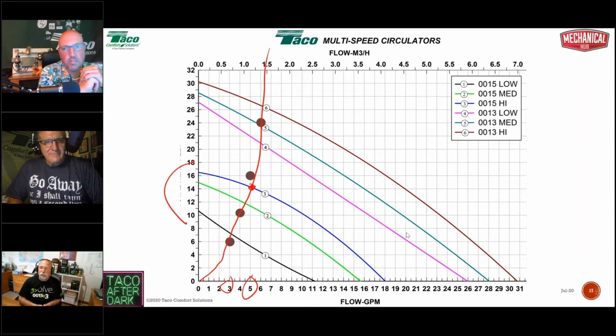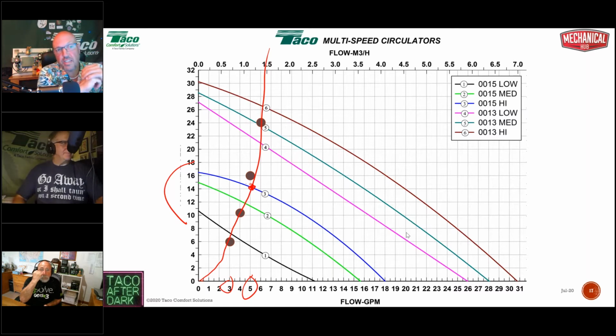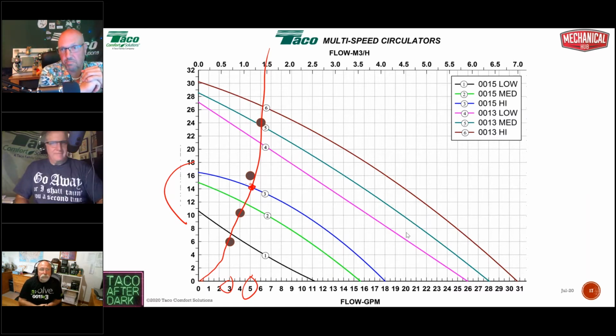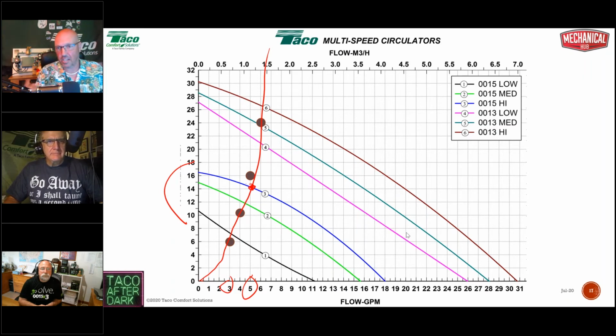Well, the other thing you need to pay attention to at that point, though, is what is the outside air temp. So be careful. If you're starting it up and it's 50 degrees outside and you choke it down and get to a 20-degree temperature drop when it's 50 outside, well, now you might be choking it too much. So you've got to take a look at what your delta T is, if you had a fixed speed circulator in the system, to make sure it's going to get you there. So if your outside design temperature is 0 and you're setting up a system and it's 35 degrees outside, now expect a 10-degree delta, not a 20.